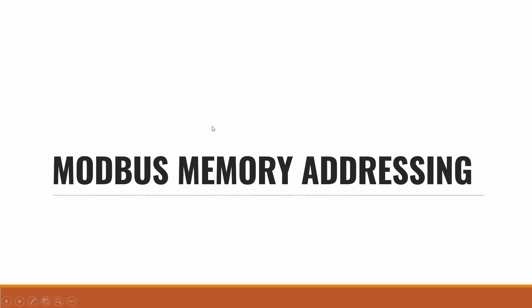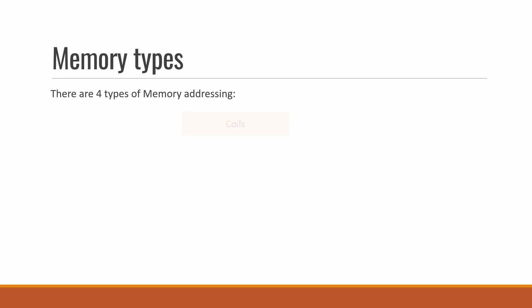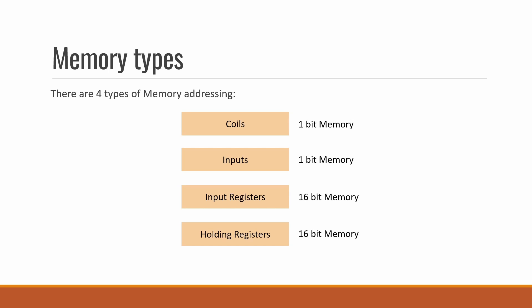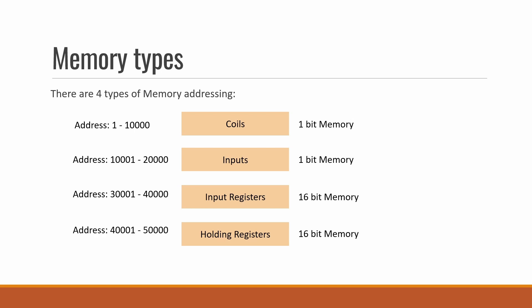Next we will discuss Modbus memory addressing. There are four data types or memory types available in Modbus: coils, inputs, input registers, and holding registers. Coils and inputs are 1-bit memory, while input registers and holding registers are 16-bit memory. The address for coils ranges from 1 to 10,000; inputs from 10,001 to 20,000; input registers from 30,001 to 40,000; and holding registers from 40,001 to 50,000. Coils are used for discrete output, inputs for discrete input, input registers for analog inputs, and holding registers for analog outputs.